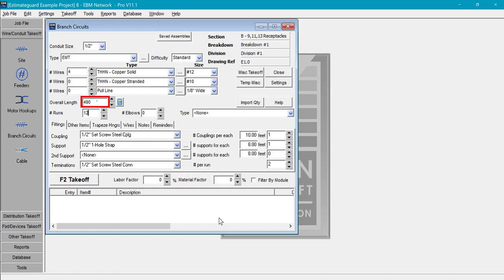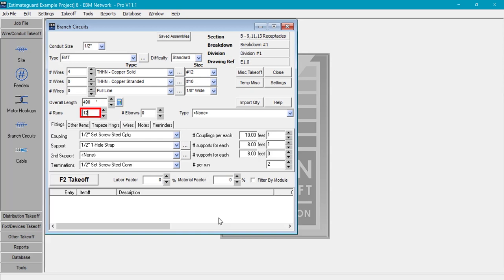After measuring the conduit length I entered the following data. Overall conduit length 490 feet. Number of runs 12. The number of runs is how many separate conduit runs there are in the entire conduit system measured. This would be how many times the conduit is broken by boxes. In other words from box to box. This tells the estimating system how many EMT connectors to include. In this case 12 runs would equal 24 connectors.